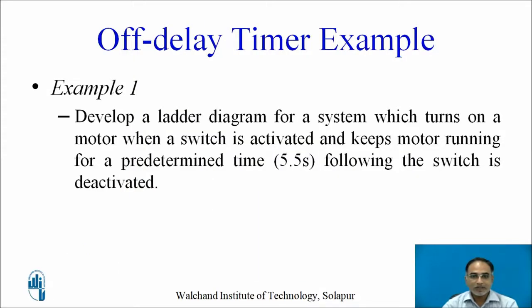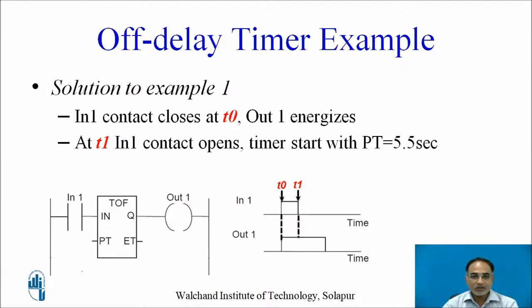Let us solve some examples with the help of the off delay timer. We will develop a ladder diagram for a system which turns on a motor when a switch is activated and keeps the motor running for a predefined time — let us say 5.5 seconds — following the switch being deactivated. A ladder rung is shown with an input switch, an output coil, and an off delay timer in between them, along with a waveform on the right hand side.